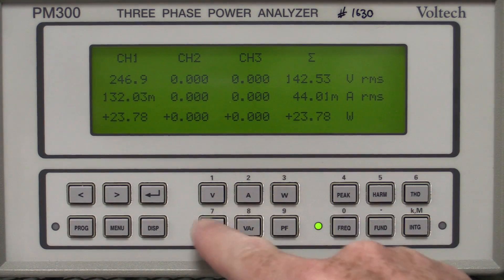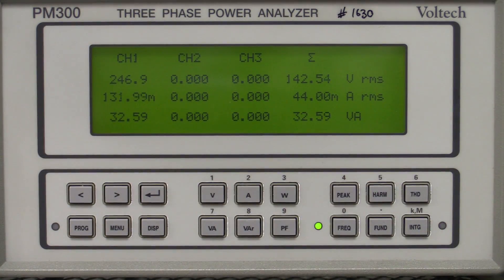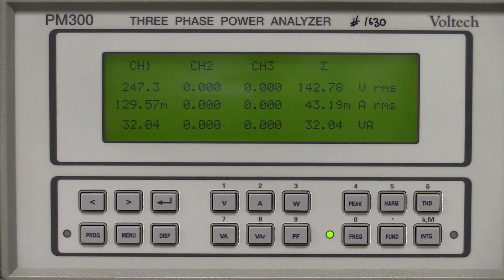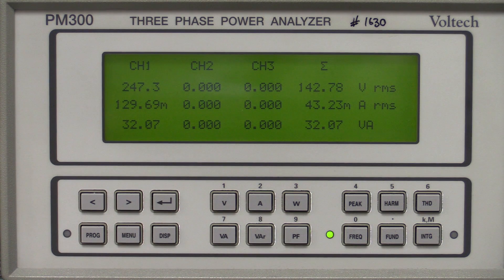But even if you don't pay for it, this apparent power is still a real problem. And of course, poor power factor like this, VA is volts times amps. So the utilities ultimately have to provide more current down the line, down the transmission line. And of course, more current down the transmission line, equals I squared R losses. The losses are squared. So of course, the utilities really take this seriously, this power factor, and they put in power factor correction.